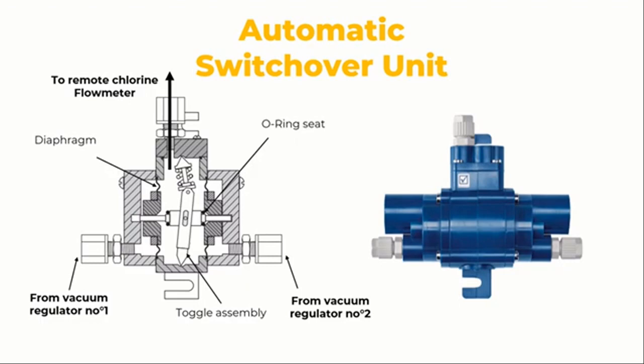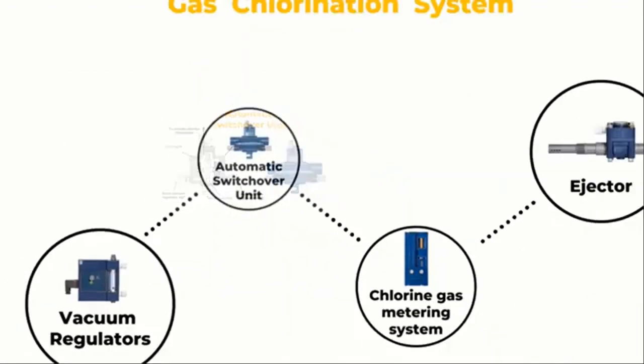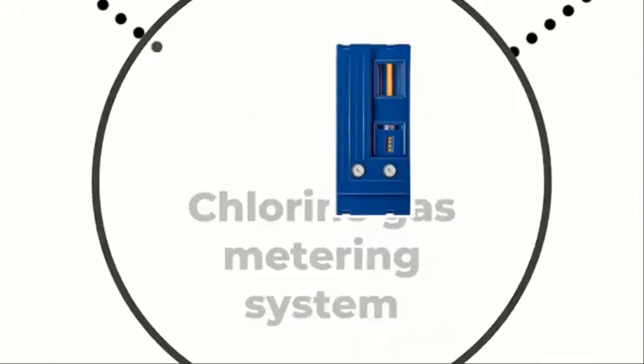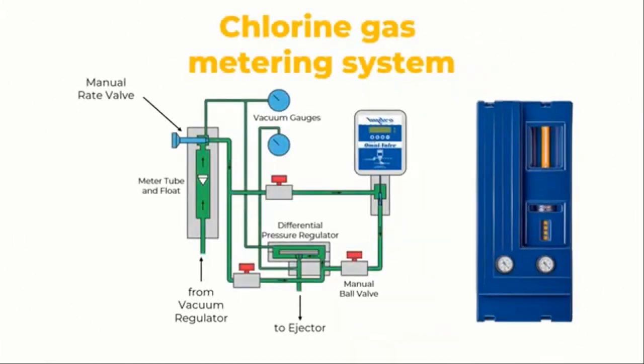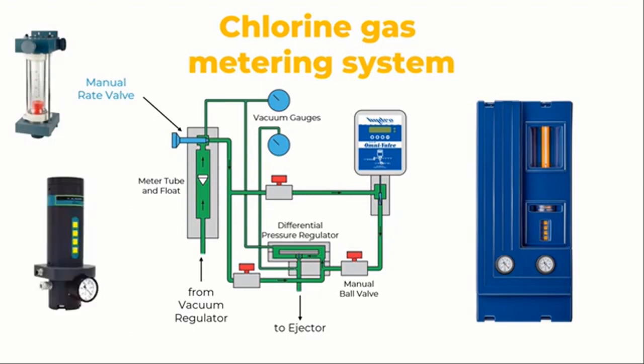The chlorine gas metering system is the third piece of equipment. It is positioned between the vacuum regulator and the ejector to provide a visible indication of the chlorine gas supply rate. A manual rate control valve will be placed after the flow meter tube in every gas chlorination system. Installation of an automatic control valve between the flow meter tube and the ejector is also possible. Differential pressure regulators are optional and can also be added.